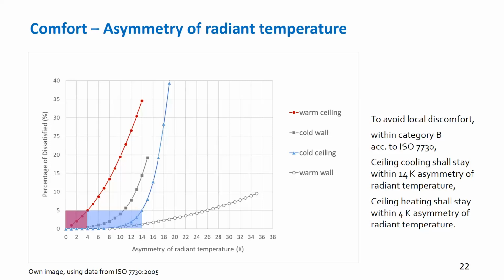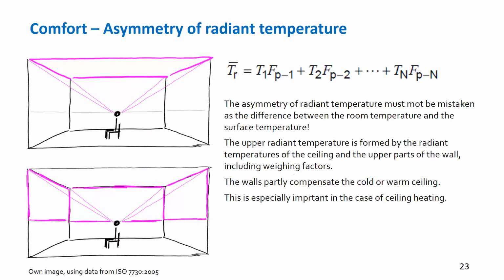So, and a big warning, a big learning is that please never misunderstand this asymmetry of radiant temperature as the allowed difference between the surface and the room. I have been in many, many discussions of designers. They said, oh, I understand, Mr. Holzer, I understand that a warm ceiling is allowed only to be 5 degrees warmer than the room temperature. No, that's not. It's about the asymmetry of the radiant temperature of the upper half and the lower half of the room. It's not the difference between the surface and the room. So never think that in a 22 degrees room, it's allowed only to heat with a 26 degree ceiling. That's not true. It can be much warmer because it's about the sum of the radiant temperatures above your head level and below your head level.